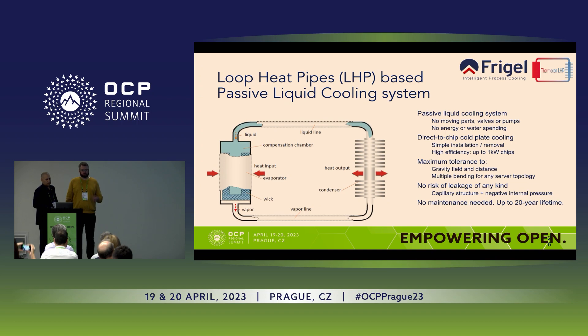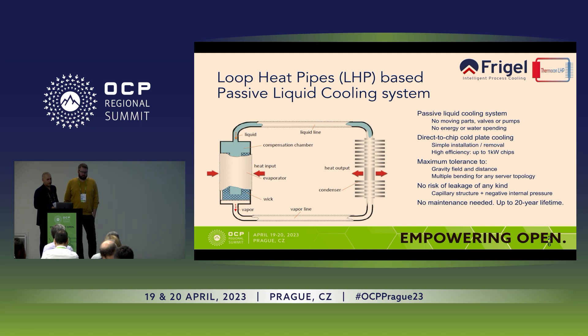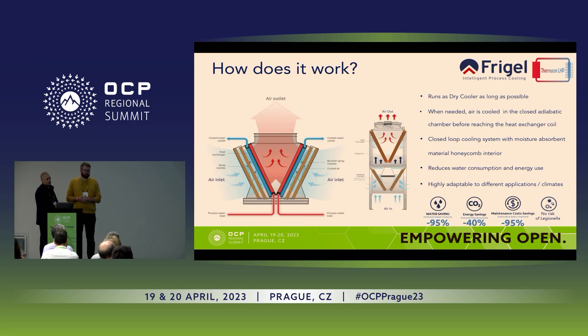This is a short explanation of the loop heat pipe and how it works. It passively transfers heat from the evaporator to the end of the rack, and it is a closed loop so there is no effect from the ambient environment. Another component is the adiabatic cooler, which requires no water treatment and has no issues with Legionella. It performs 95% of its work as a dry cooler.